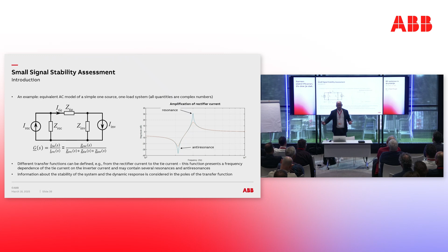To know when and if it will oscillate, we need to derive the system transfer function like written here. This transfer function gives us the resonance point or the anti-resonance point. It can happen that we don't care, because every such network will have resonance and anti-resonance points, you can't avoid it. But what I care about is where the resonance point is. For example, if this resonance point is at 300 hertz, and I happen to have an uncontrolled rectifier that creates a ripple of exactly 300 hertz, then guess what? This is going to get amplified. This is something you need to predict when designing the DC system.